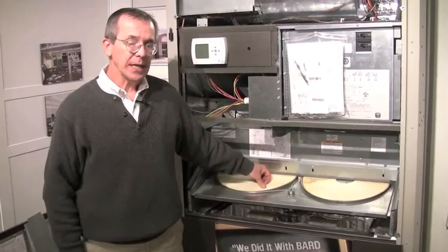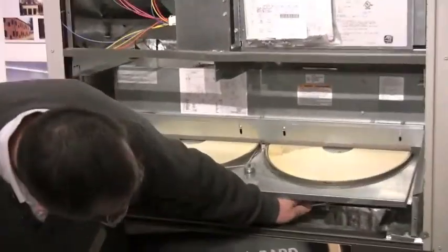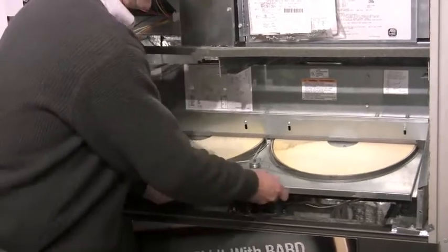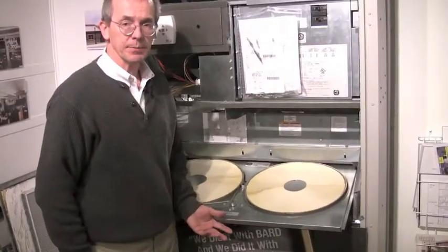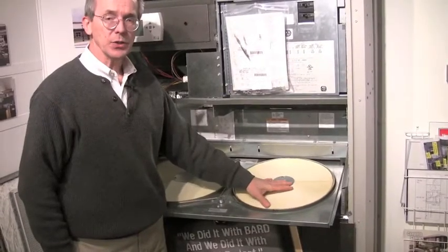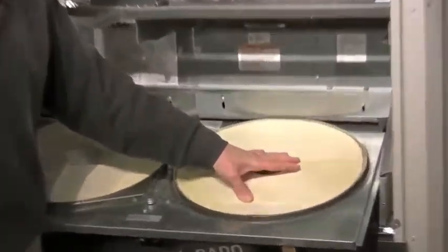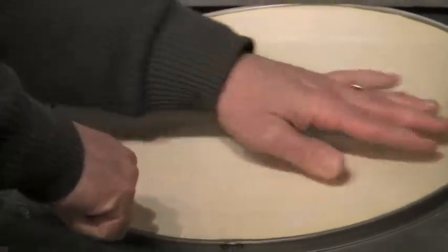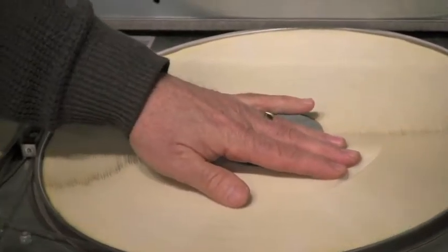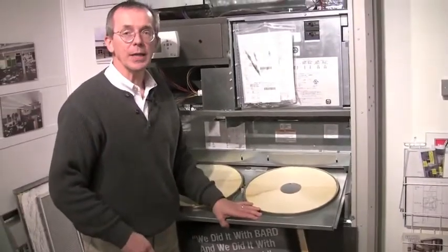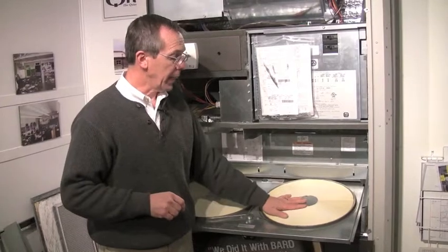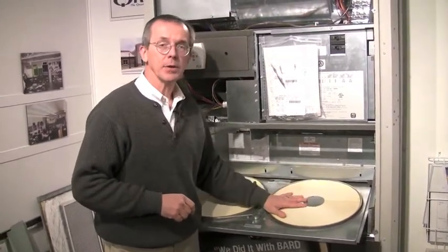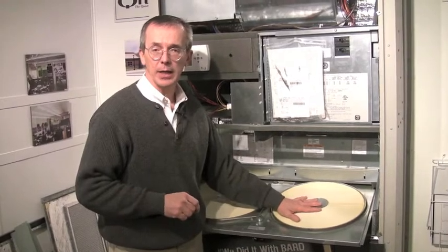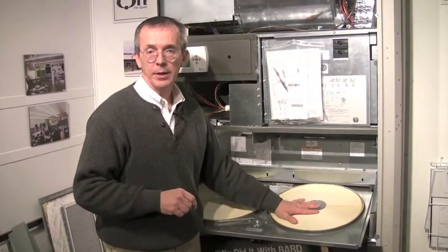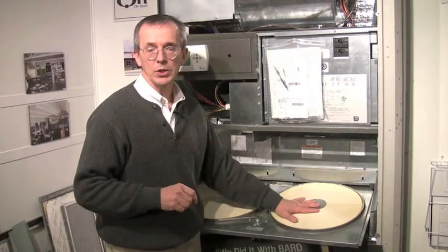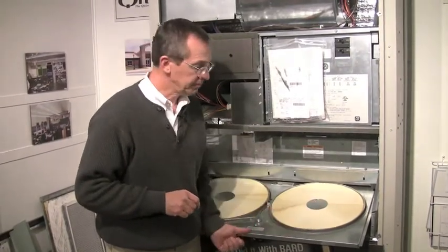The ERV wheels are easy to maintain. There's a Molex plug here. Unplug it and this whole cassette will slide out for service. To clean the wheels, the installation instructions from Bard indicate that you can do just this with a vacuum cleaner and a brush and vacuum off each section of the wheel independently. Bard also indicates that you can take the cassette out, take the wheels out, spray some cleaner on it, an alkaline cleaner, something like 409, spray it on the wheels, scrub them a little bit, rinse them off, let them dry, and put them back in.